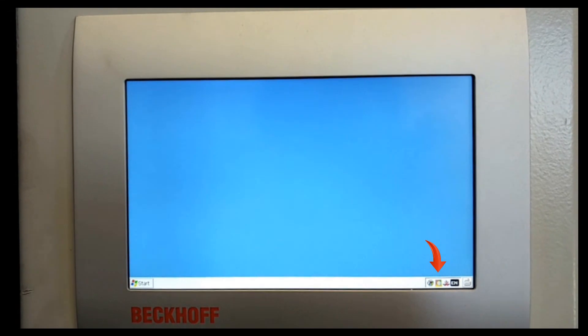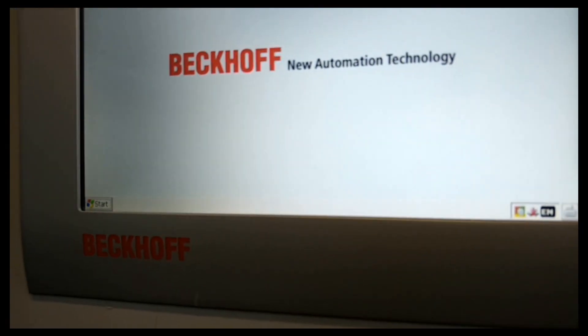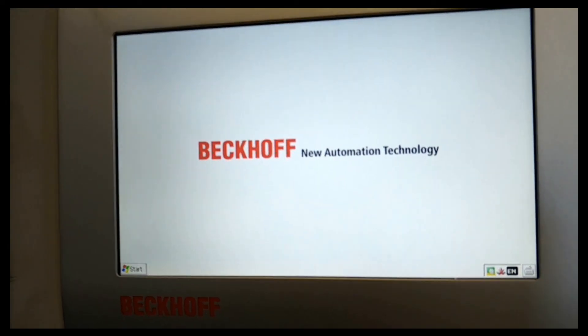After inserting the micro SD into the CX1920 and powering up the controller, it will first boot into the operating system. In the right-side corner, you will see the TwinCAT icon show a color, indicating the system is reading files from the micro SD. After reading is complete, the system will reboot and automatically upgrade to the latest firmware. This whole process takes about one minute. You'll see the icon continue to indicate activity after the second boot, and once the icon turns green, the upgrade is complete.